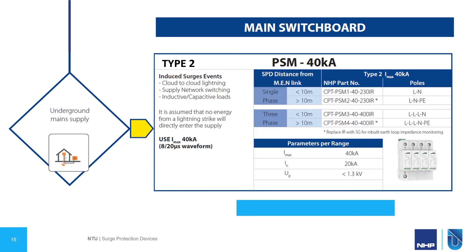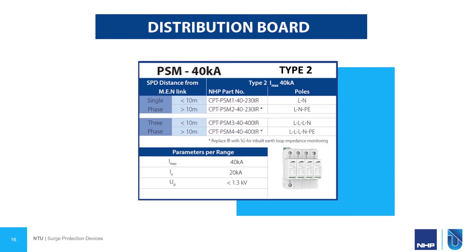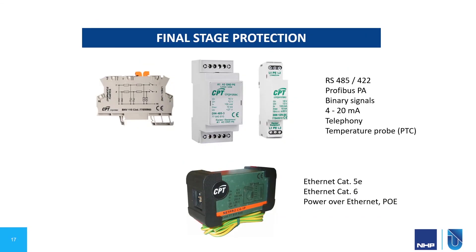So that covers the first stage of protection in our main switchboards. However, it's always recommended to have a second stage of protection in our distribution boards. This is to protect from residual surges coming from our main installation, as well as surges being induced on the cable between the main switchboard and the distribution boards, and any surges coming from switching of our loads. In this case, the PSM 40 kA Type 2 device can be used as well. For any particularly sensitive electrical equipment, there is a range of final-stage surge protection devices available, installed as close as possible to the sensitive equipment to capture the remnants of any surges on your network.